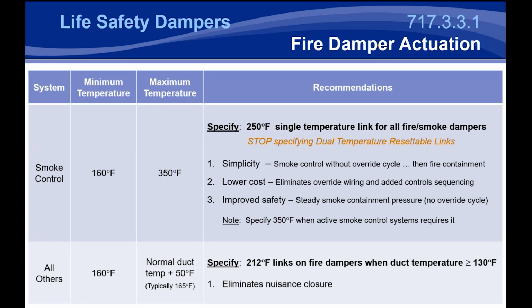Any of these dampers that have an actuator are going to have a torque requirement to operate, but they're set to operate and tested at ambient and then temperatures added, like you would see if a fire affected a building. So as the testing goes, you start with a damper at say 2000 FPM, your minimum velocity, and then for a damper rated at 350, you heat that air to make sure that damper operates at 350. Now with that constant CFM volume to get that 2000 feet per minute in the static duct size, you are actually increasing the overall relative velocity that that damper sees. So there's much added torque to certify a damper at 350 than at 250. That's why if your system isn't going to operate at that, I definitely recommend specifying the damper close at 250.